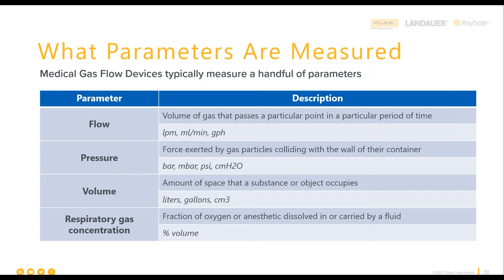Going back to the balloon: pressure would be how 'hard' the balloon becomes as the tension of the balloon itself pushes back on the air pressure inside. We had flow as how the air travels from me into the balloon, and now pressure is how hard that balloon is — in that case, the vessel is the balloon. Pressure can be measured in bar, millibar, psi, or centimeters of water depending on the service manual. When you think about test equipment, you may need to flex across those units and switch them on the fly.